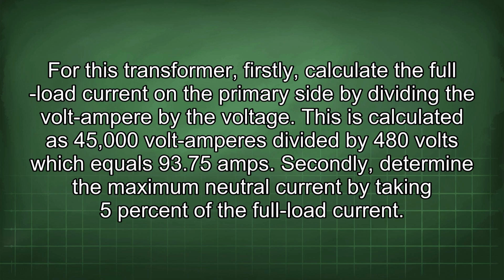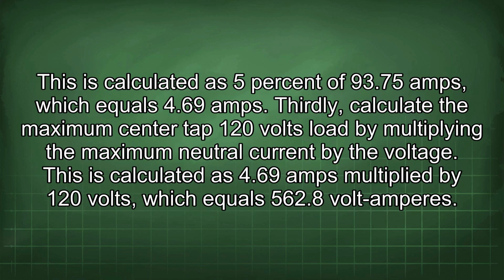Secondly, determine the maximum neutral current by taking 5% of the full load current. This is calculated as 5% of 93.75 amps, which equals 4.69 amps. Thirdly, calculate the maximum center tap 120 volts load by multiplying the maximum neutral current by the voltage. This is calculated as 4.69 amps multiplied by 120 volts, which equals 562.8 volt-amperes.